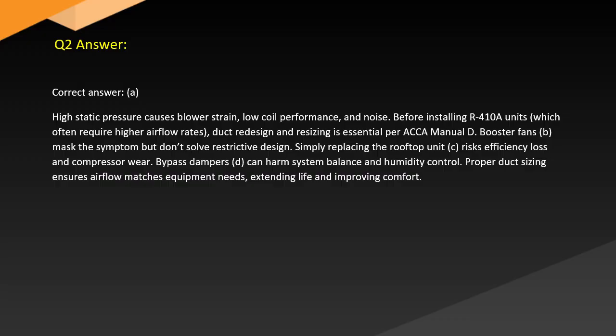Answer. Correct answer: A. High static pressure causes blower strain, low coil performance, and noise. Before installing R410A units, which often require higher airflow rates, duct redesign and resizing is essential per the manual. B. Booster fans mask the symptom but don't solve restrictive design. C. Simply replacing the rooftop unit risks efficiency loss and compressor wear. D. Bypass dampers can harm system balance. Proper duct sizing ensures airflow matches equipment needs, extending life and improving comfort.